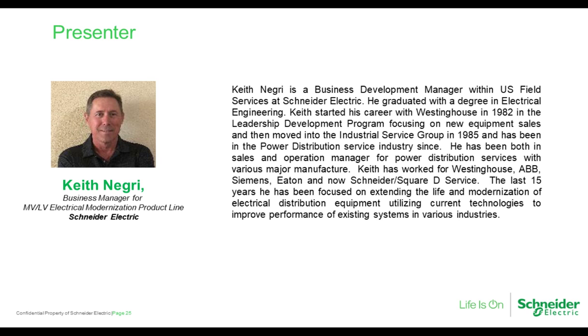We have time for one more question. It's please talk about arc flash resistant gear and 100% rated versus 80% rated breaker ratings. Okay. Most of the arc flash resistant gear right now is developed in the medium voltage and low voltage switchgear standards. And those breakers are 100% rated breakers, so it's really not going to affect those. As we get down into switchboards and panel boards, it shouldn't change what that breaker is, whether it was an 80% rated breaker or a 100% rated breaker.